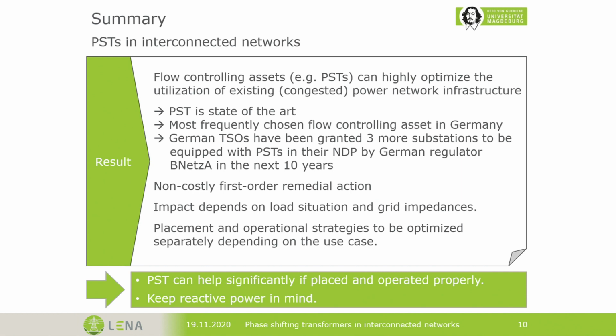We don't want to make these PSTs fight against each other. So planning and operation strategies need to be optimized best in combination with each other. So if you install PSTs in your grid, this can really help you if you do it properly. And one last word from my side, it's very important that you keep reactive power in mind and plan for compensation because these PSTs really need a lot of reactive power.